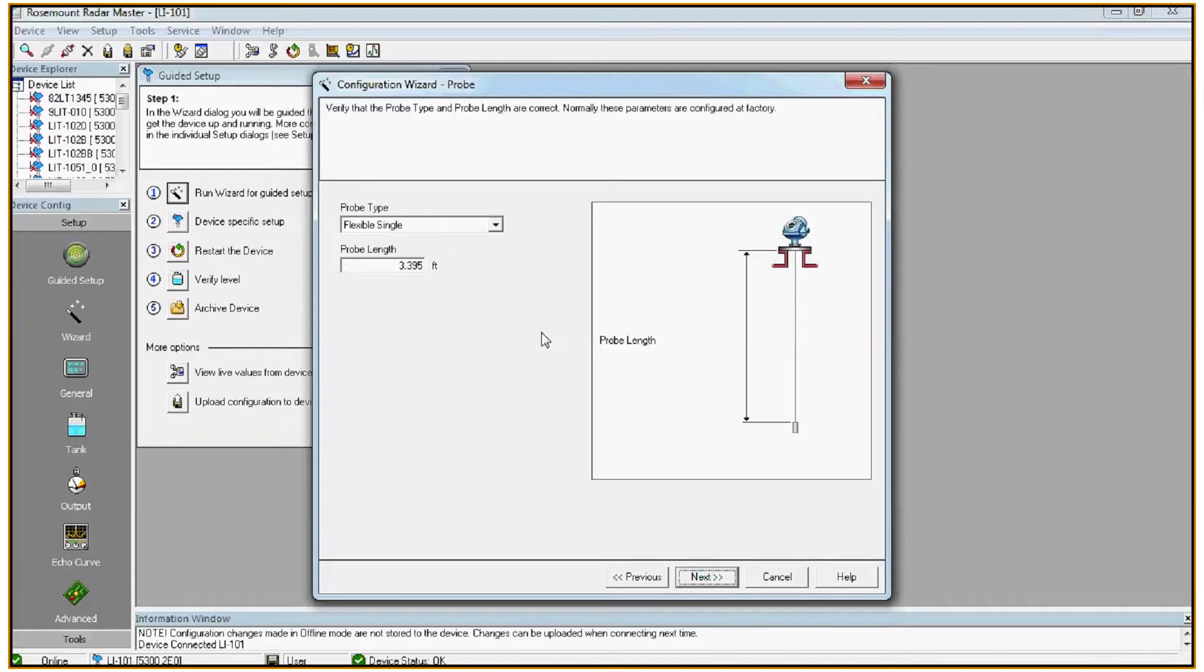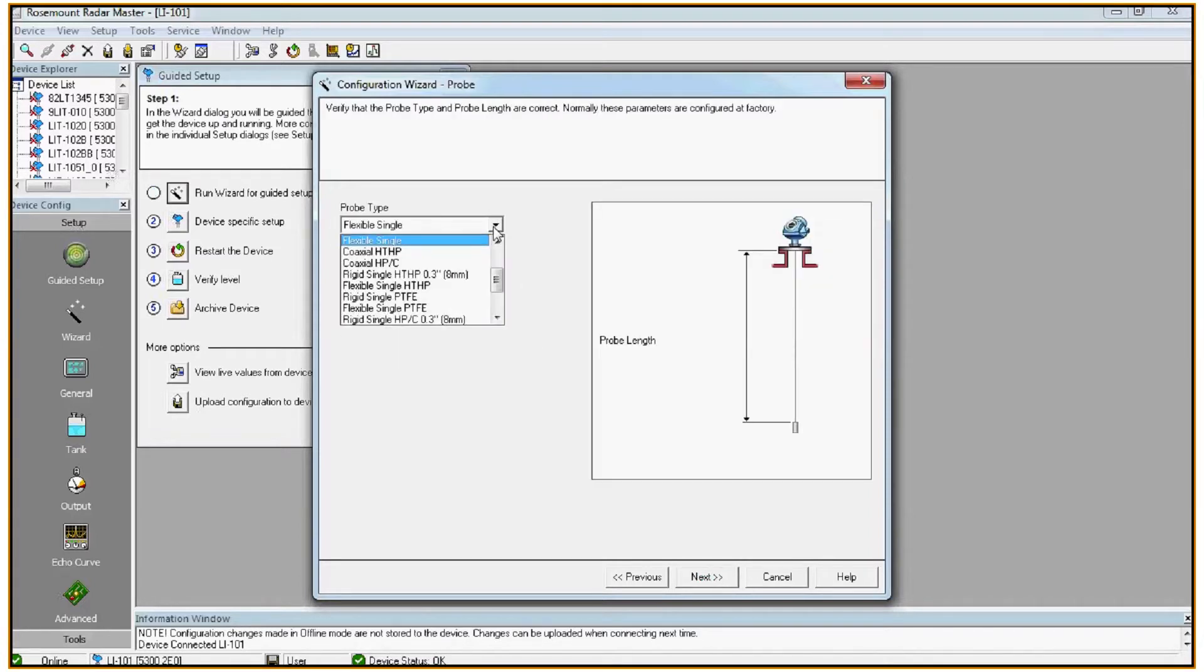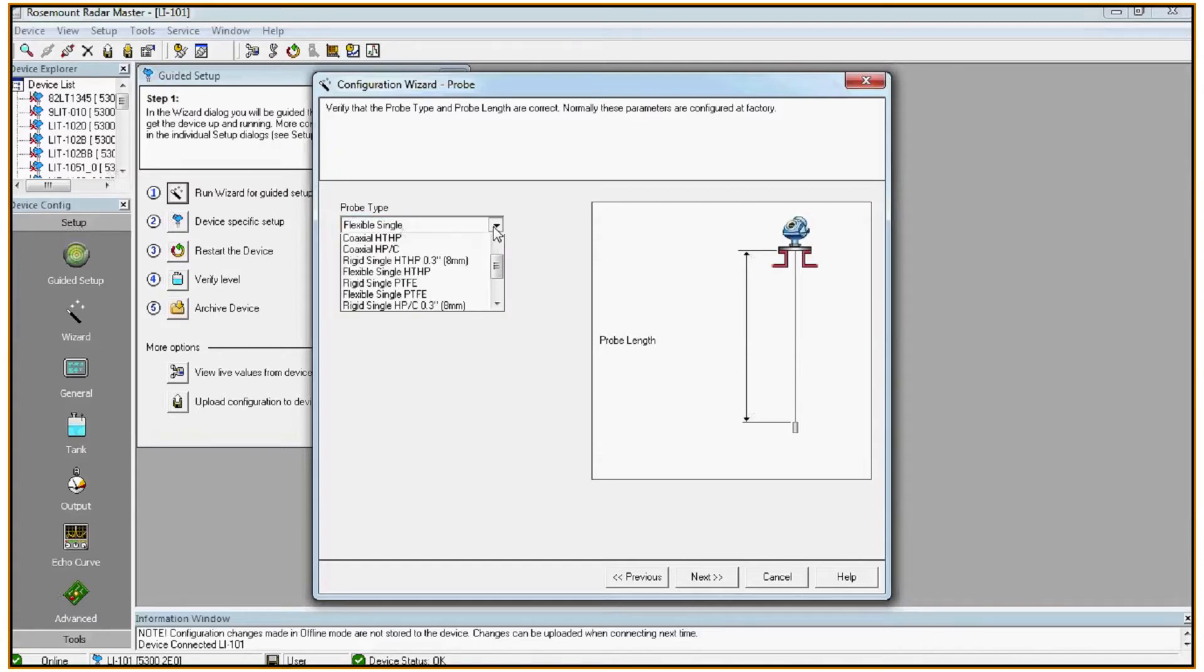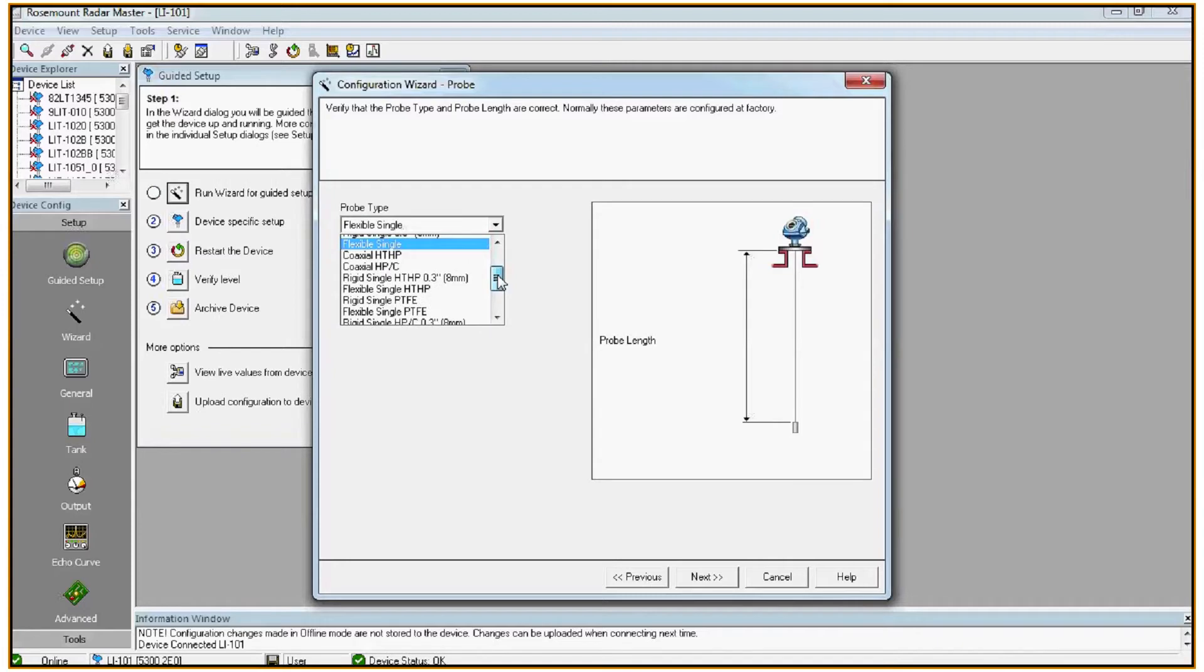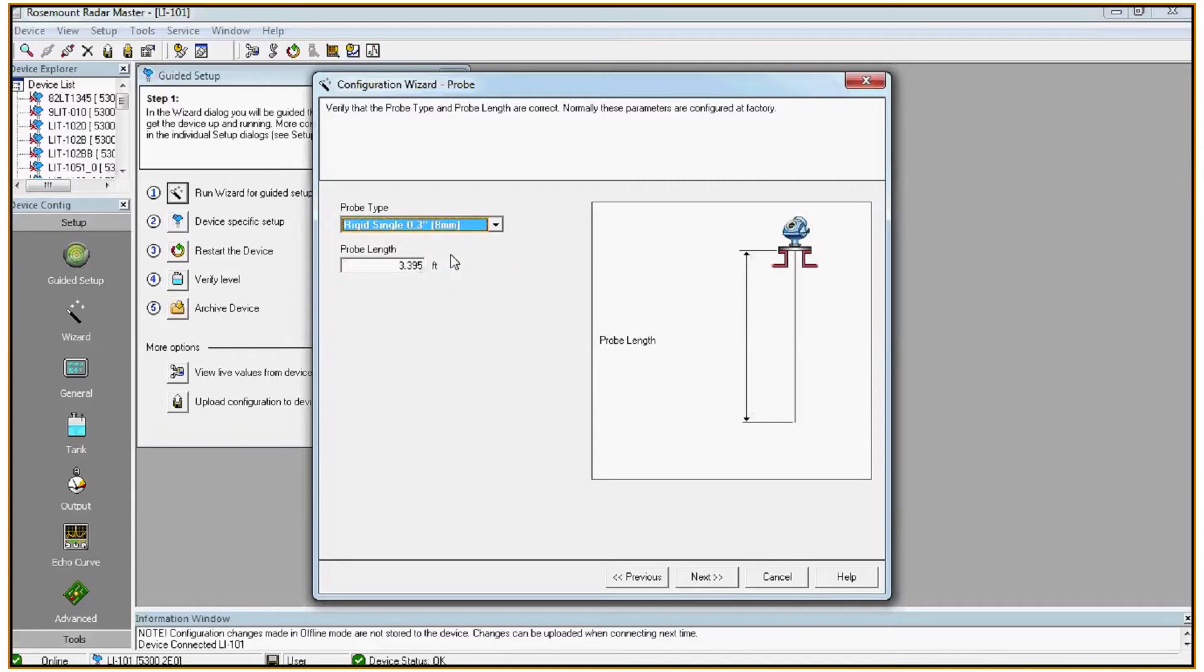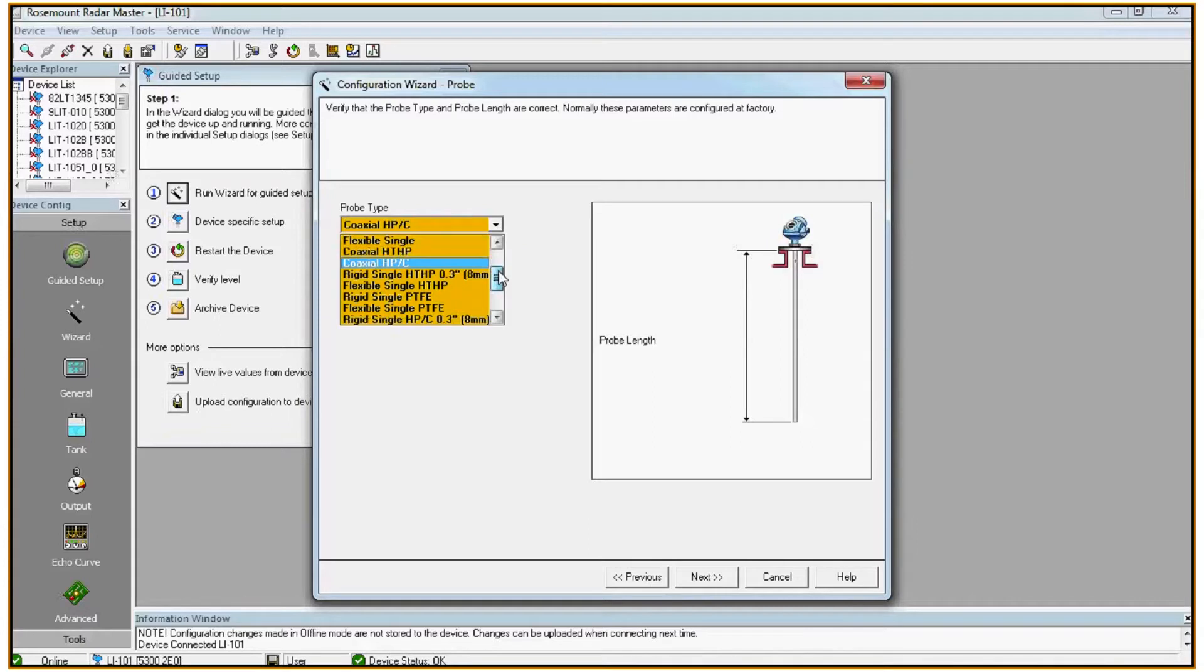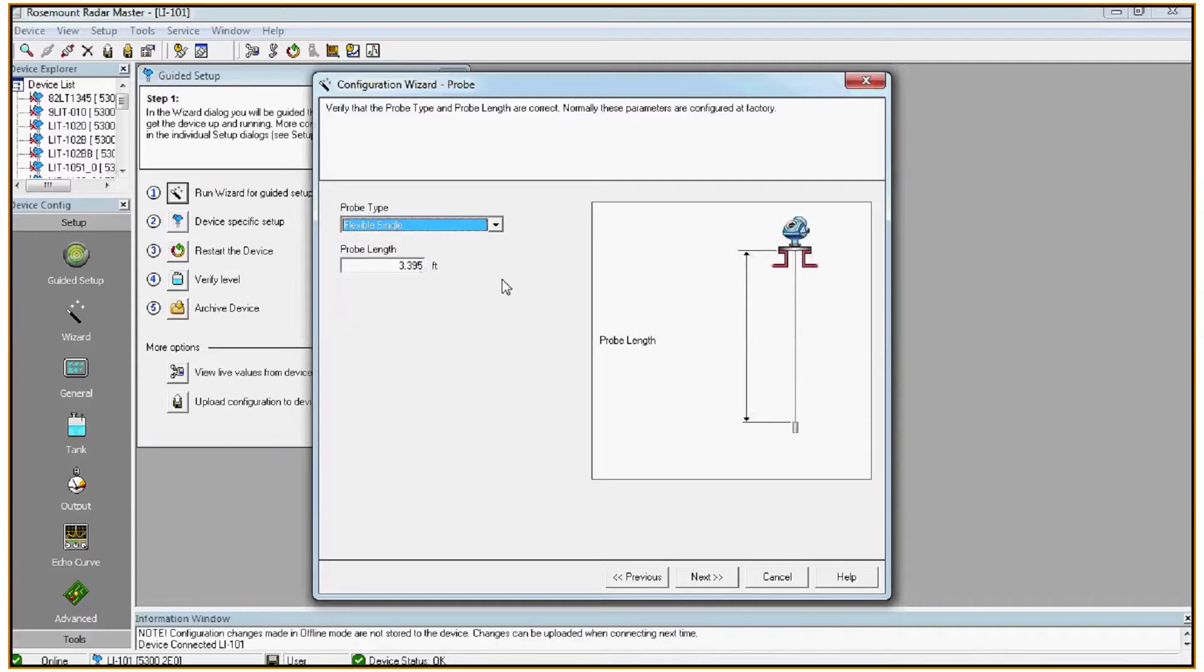Here we configure the type of probe that the transmitter is connected to. This should be configured from factory. If you're unsure, please reference the model number on the transmitter and check it against the product data sheet. If you change any of these selections, the picture to the right will update and give you a reference as to how to measure the probe length. In this case we're using a flexible single and the probe length is always measured from the bottom of the flange to the bottom of the weight.